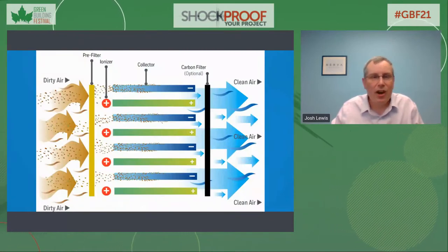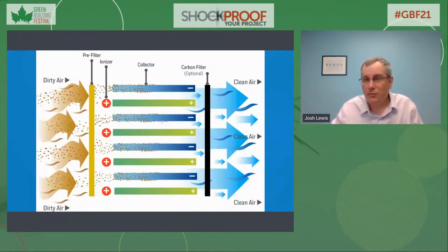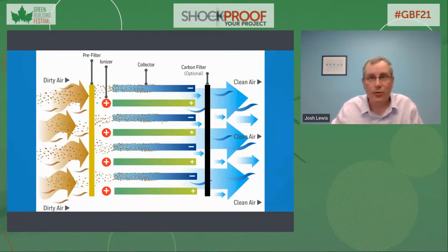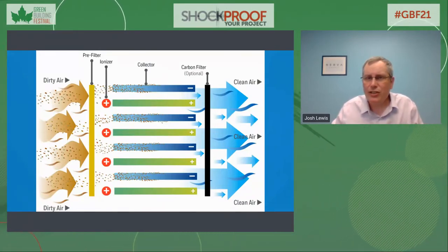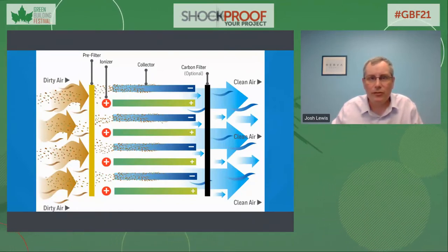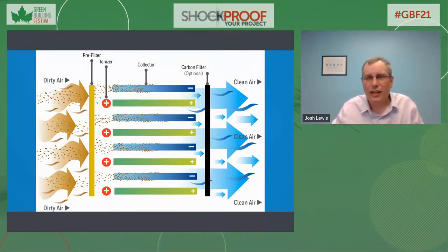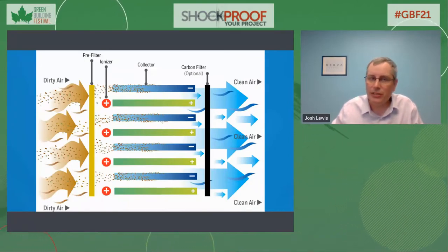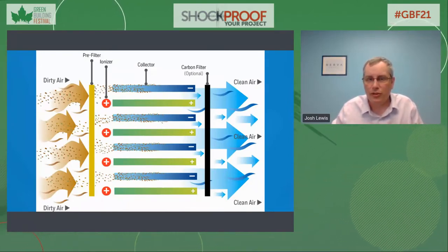There is a non-conventional filtration option available that can provide both high filtration and superior energy performance. Electrostatic air filters separate themselves from pleated filters by using electricity to catch dust, pollen, and other airborne particles. They can achieve a high MERV rating with a low amount of differential pressure, as they have large openings which rely on the electrical charge to capture and hold the airborne contaminants. While electrostatic filters have a higher upfront cost, they typically have a lower cost of ownership over their life cycle, because when dirty, they only require the filter media to be washed, not replaced.